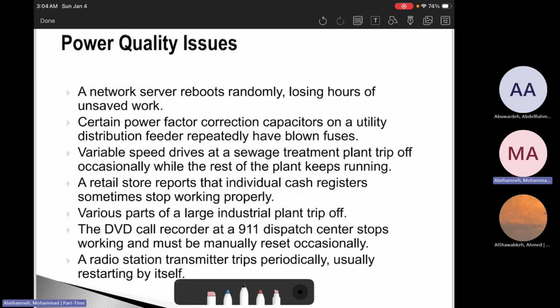Especially assume that you are at the cash register, and suddenly, in the middle of the work, it starts rebooting. This will be very annoying. The other thing is 911 dispatch. The 911 recorder stops and needs resets. This shows power quality can become life critical if critical systems are not designed with proper ride-through. For example, 911, the emergency lines, if they have a poor design, if they don't have a UPS, an uninterruptible power supply, or a redundant supply, then small power quality events become operational hazards and can create problems.